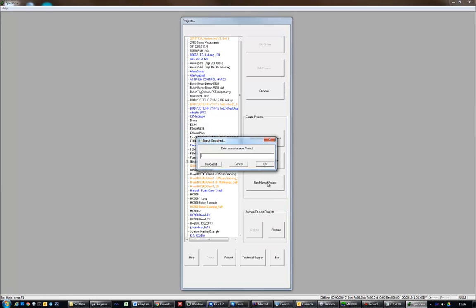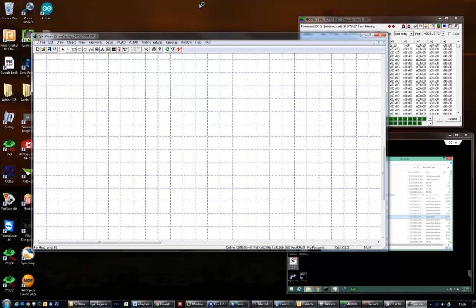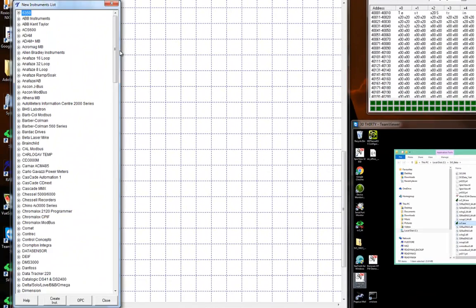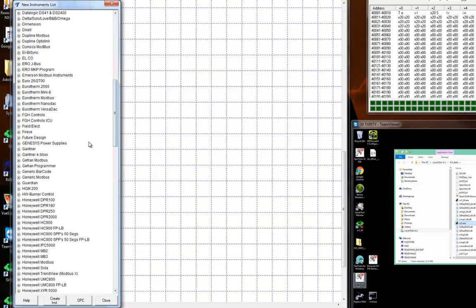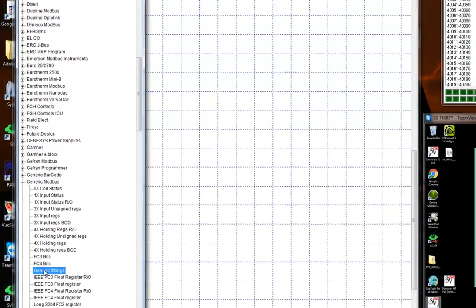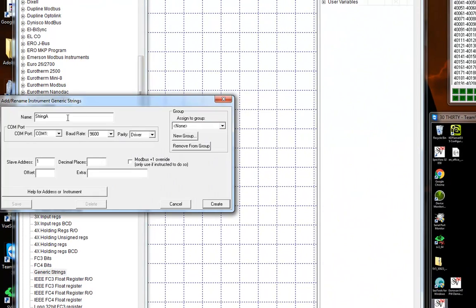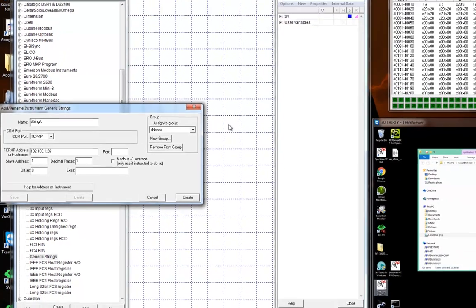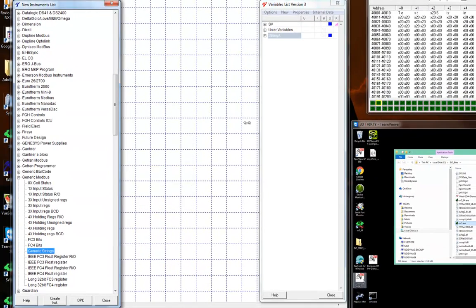I'm going to call this project 'string testing'. In our Generic Modbus driver, which we got from the templates list under Generic Modbus, there are some generic strings. I'm going to create the first string, String A, at the address of my computer: 192.168.1.26, slave address 1, decimal places 1, and an offset of 0. This means that this string will be coming from address 0 in the Modbus Simulator. So I'm going to create that string — it's popped into existence here.